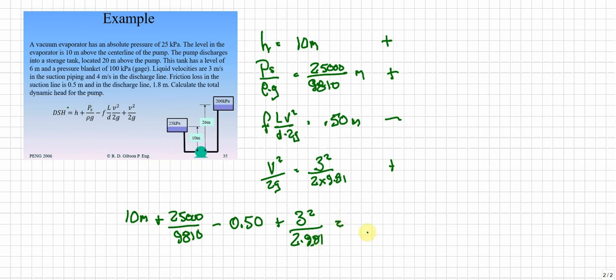And that all equals 12.5 meters. So that 12.5 meters would be reduced from whatever the net pump discharge head is, because that's helping us overcome that on that side. So hopefully that helps.